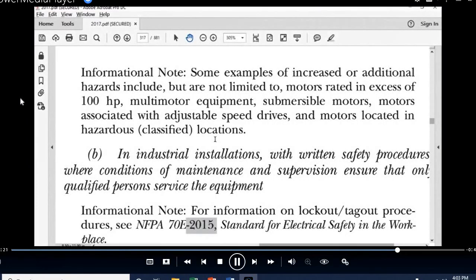It is an adjustable speed drive. Right. It's because we're talking about the disconnect for the motor. An adjustable speed drive is not a motor. Well, and you can't, I shouldn't say you can't. I don't want to say that. Most of the time, it's not smart to put a disconnect after a drive. That needs to be ahead of the drive. That's what this is saying. Right. It would induce additional hazards. So adjustable speed drives, or maybe a classified location. Sure. Don't put the disconnect in a classified location. So there are some provisions, but it's very, very limited.